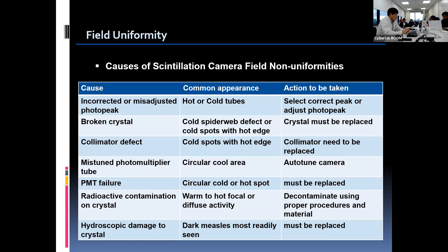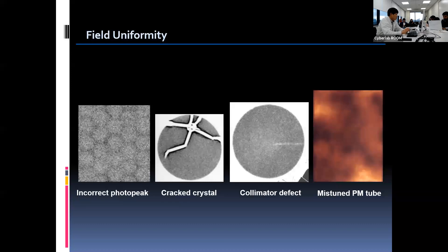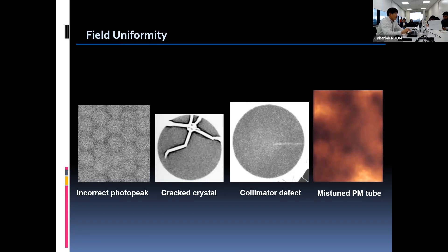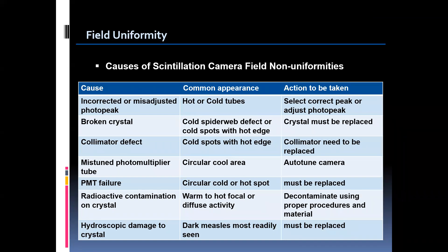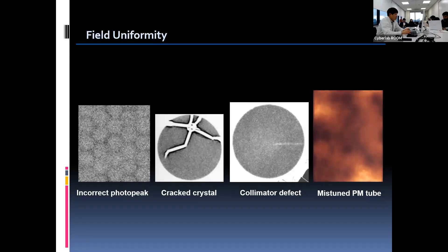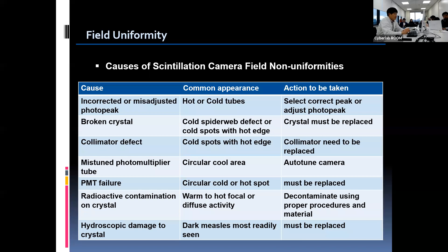This table shows examples of non-uniformity. Incorrect or mis-adjusted photopeak causes hot or cold tubes, as described in the image on the left — the PM tube shape is visualized. In this case, selecting the correct peak can take care of this problem. A broken crystal shows a cold spiderweb defect or cold spots with hot edge, as shown in the second image. In this case, the crystal must be replaced.